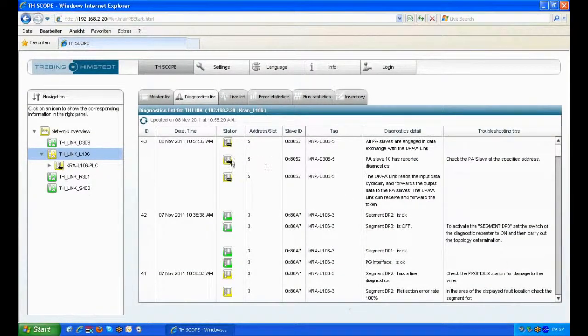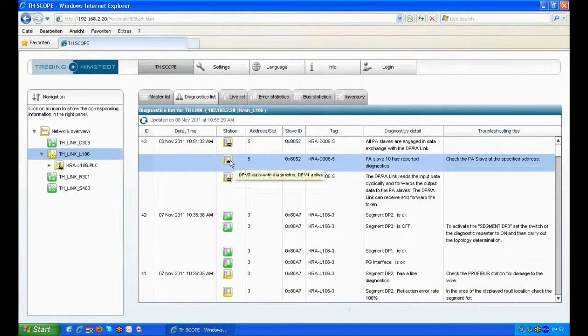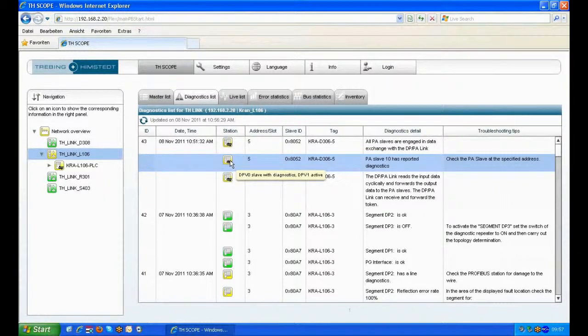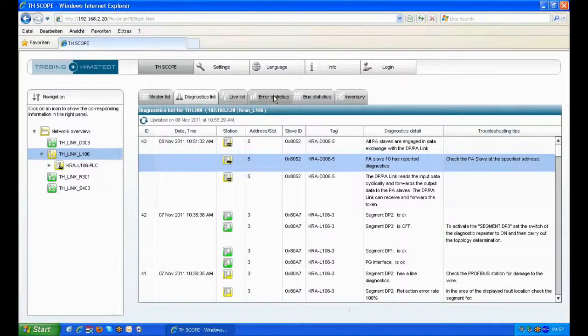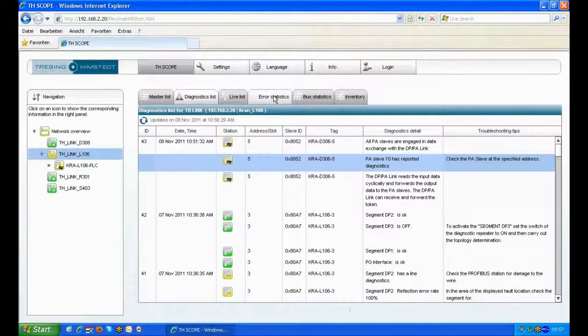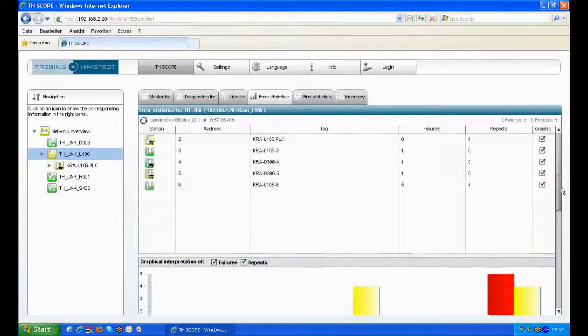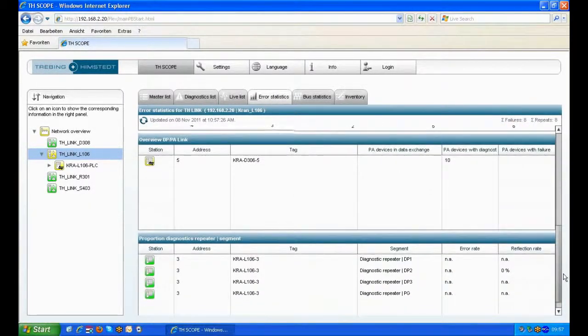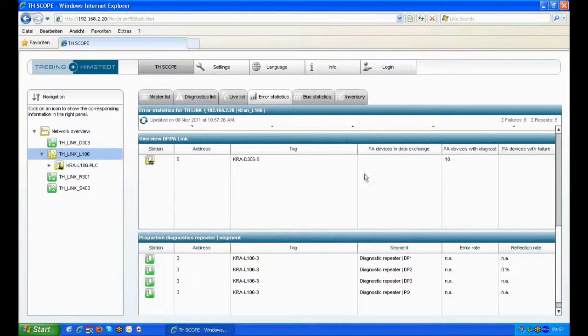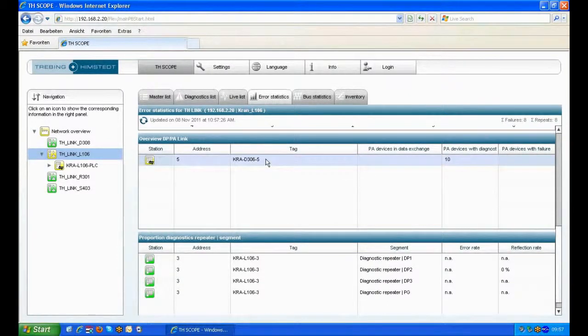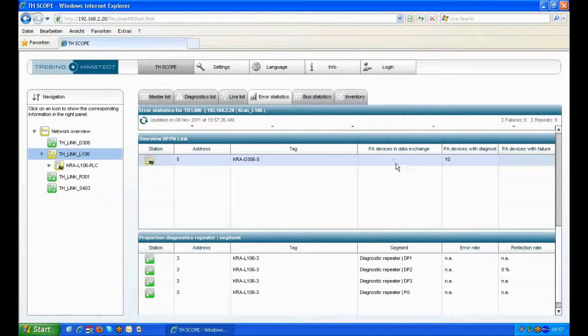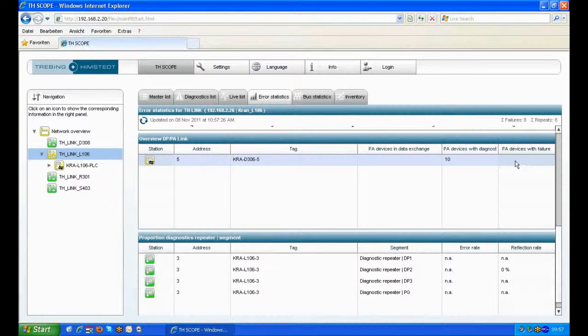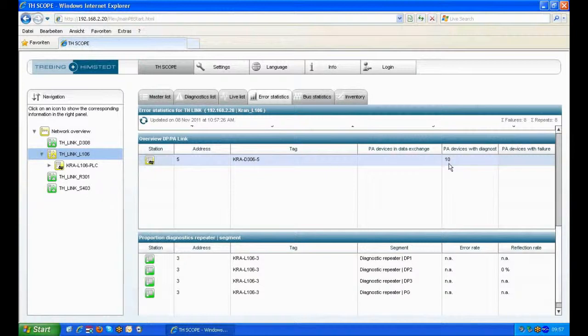On the diagnostic list you can see that the DP slave on address 5 causes some diagnostics information. We can move to the error statistics overview and there you see the DPPA Link as a non-transparent coupler and all the available PA devices behind the DPPA coupler. In this case we have one PA device on PA address 10 with diagnostics. That's what we display here in error statistics.